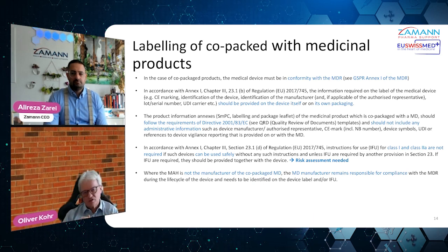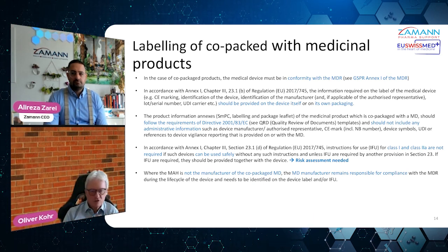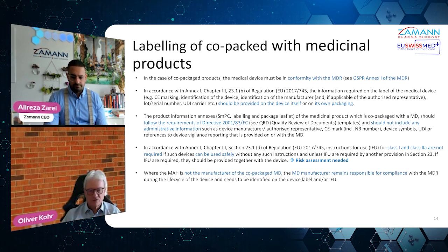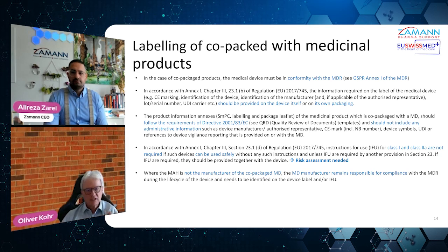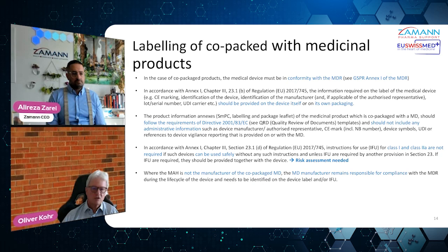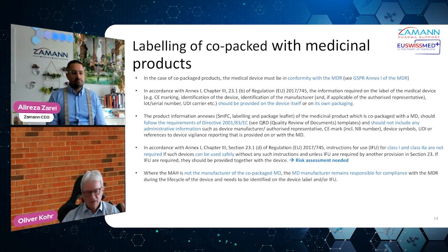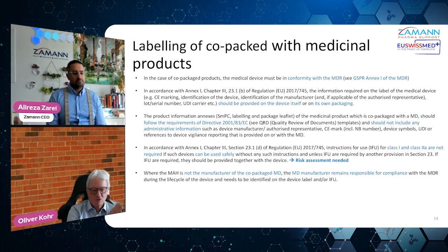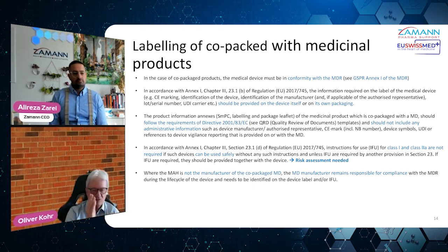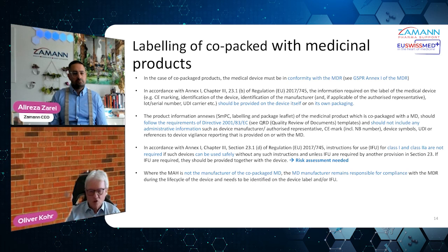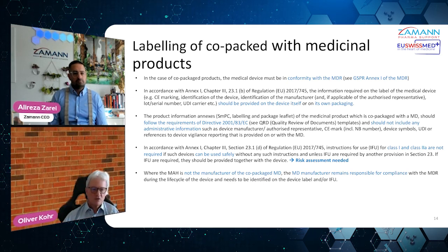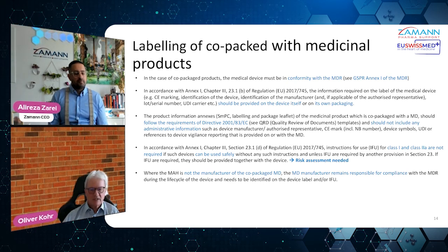So you have to make sure, as I mentioned earlier, you comply post-market, also post-market surveillance, all this work, the full thing. You have to have a full dossier with you, a technical file or tech file, as you may know it, coming from, say, the target product profile you may see at the very early stage, design description, subsystem, design requirements, all the way through the whole V model. Everything you have to have in your file, so to speak. That's key for that. And that will be checked.